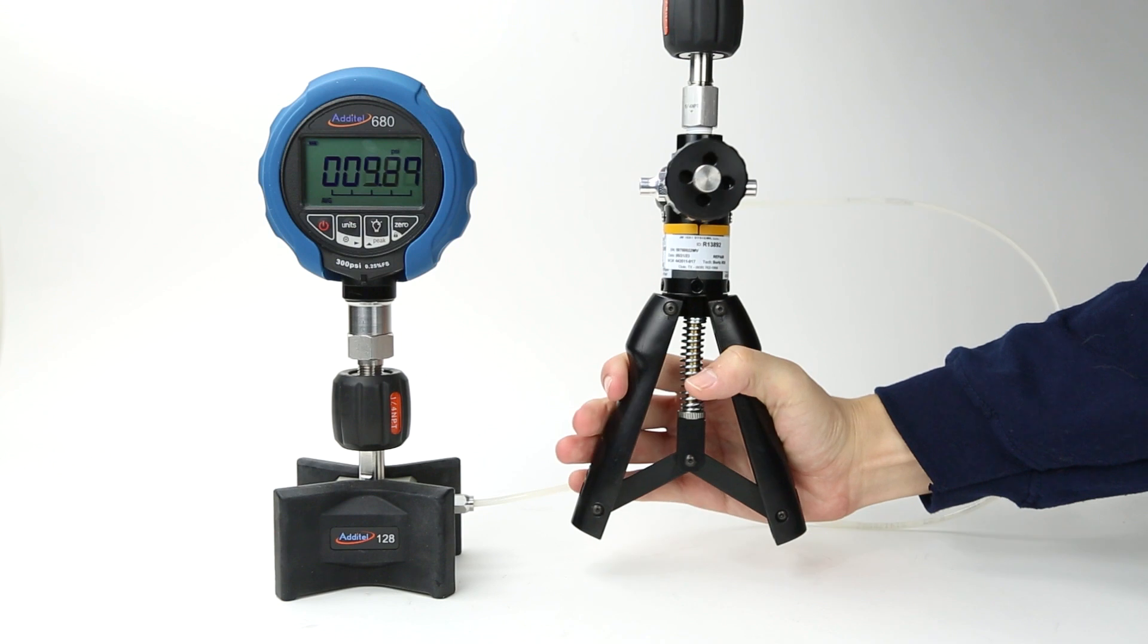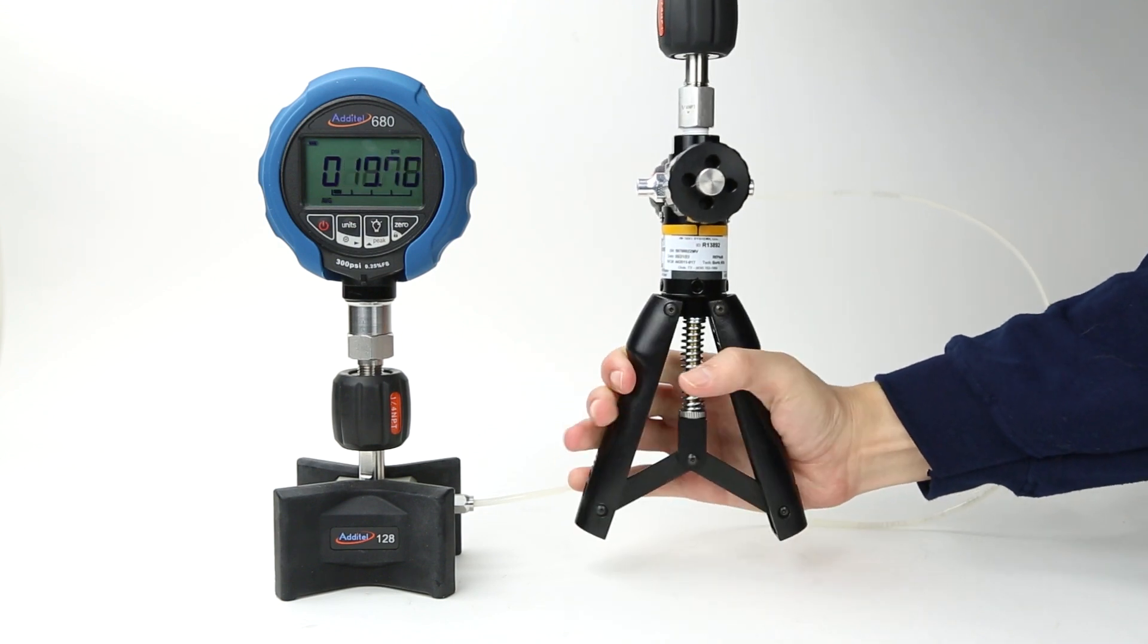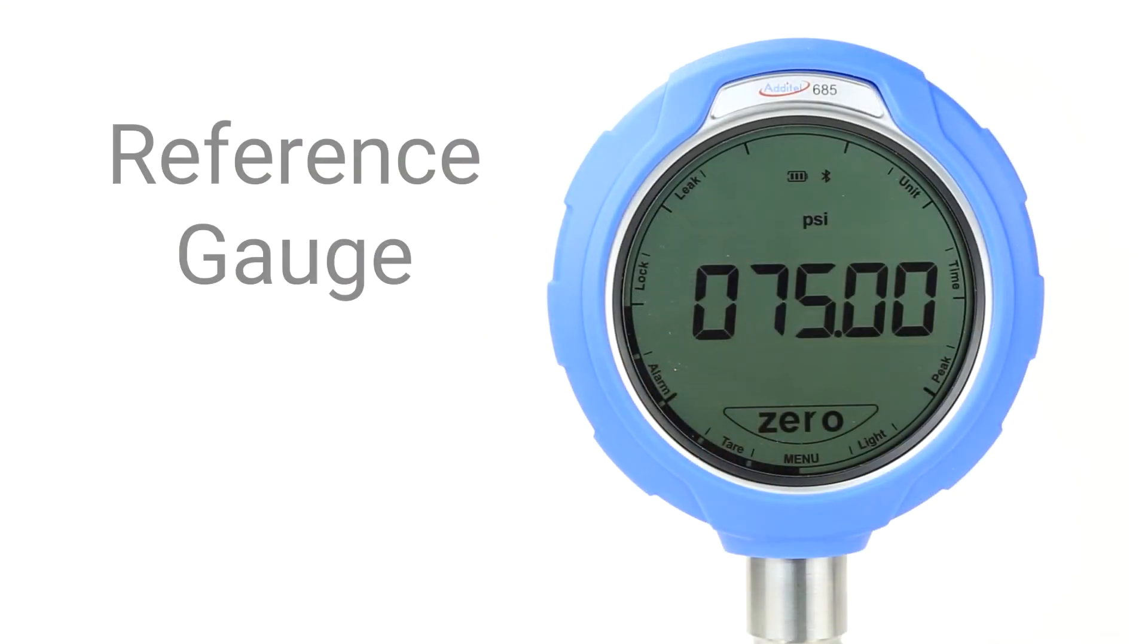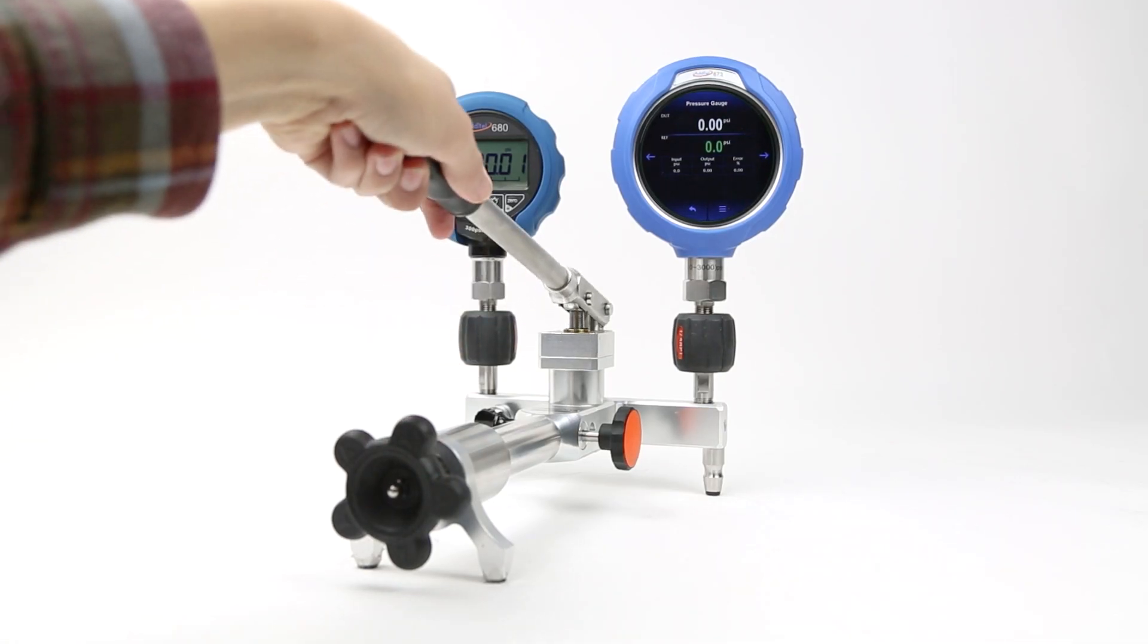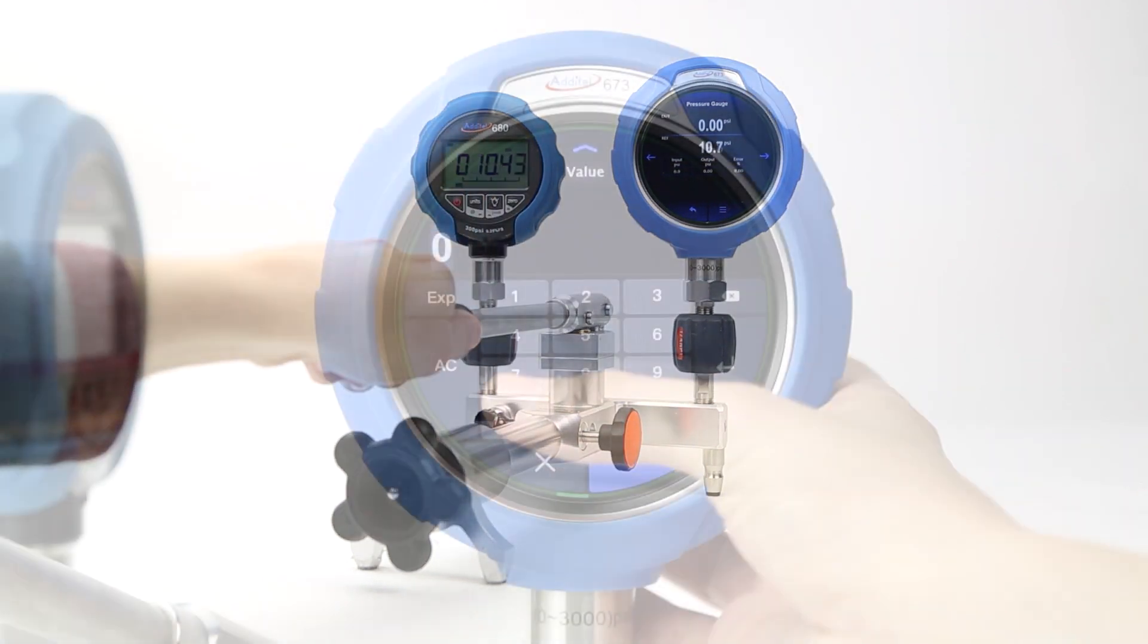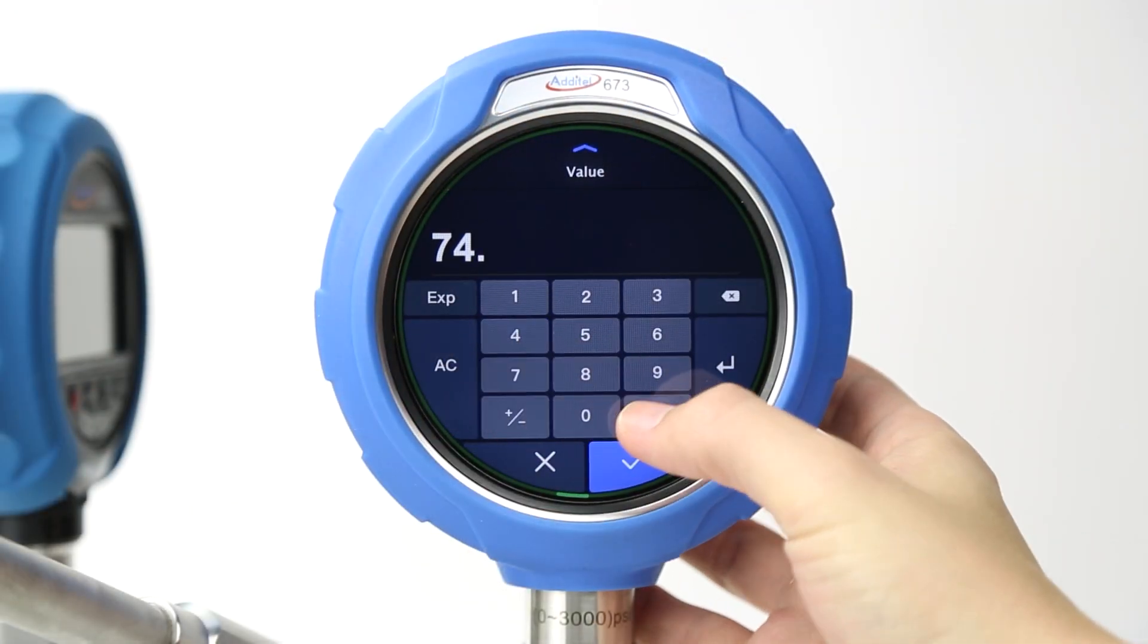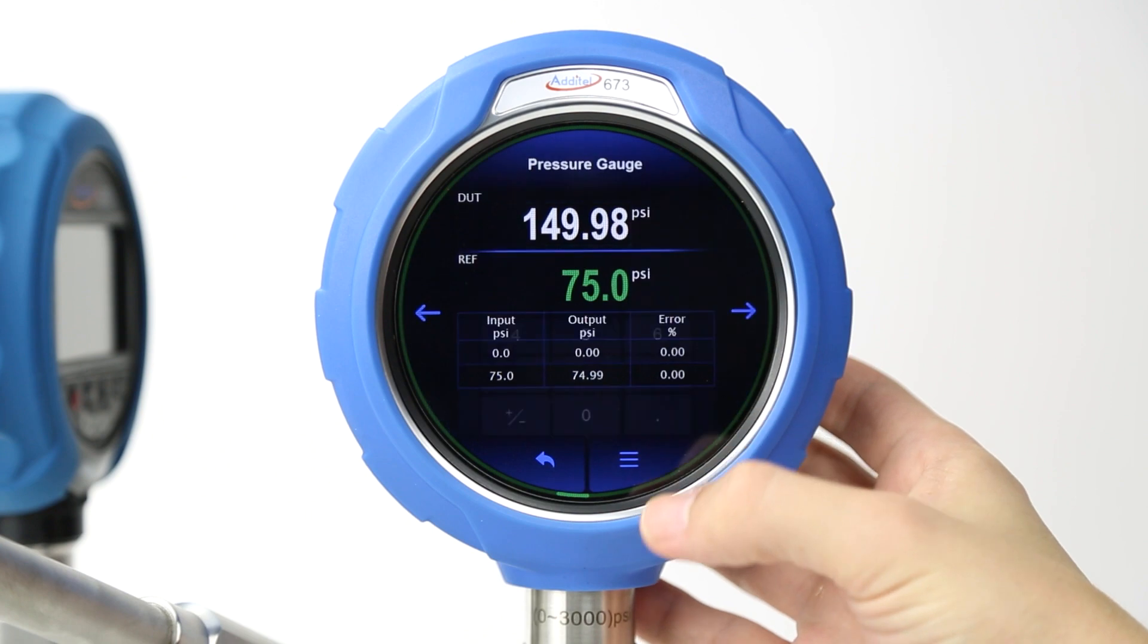To move to the next set point, Technician 1 will begin to generate pressure using the hand pump. Once they have a steady pressure, as shown on the reference gauge, they will write down the reading shown on the gauge under test. Technician 2 will use an Additel pump to generate pressure, and enter the reading into the 673, which will record its own reference pressure automatically.